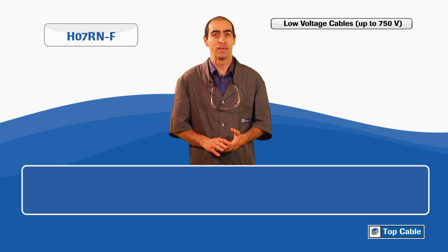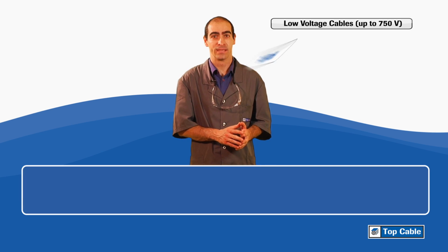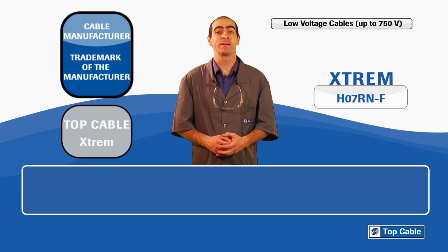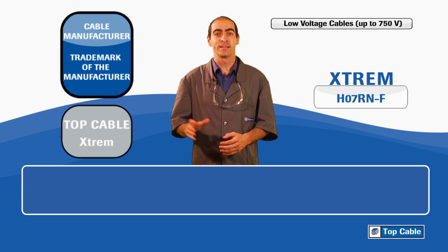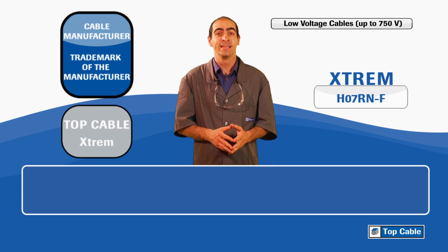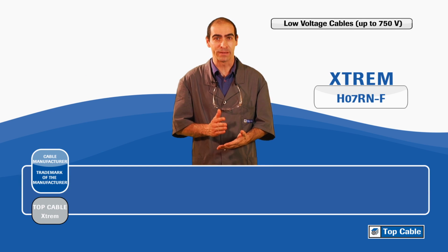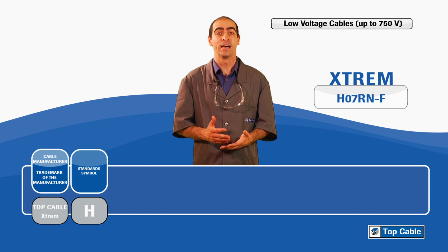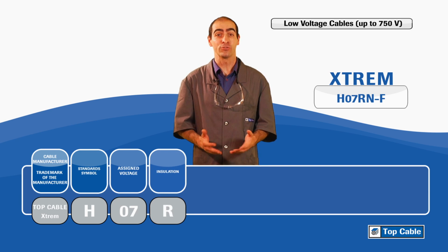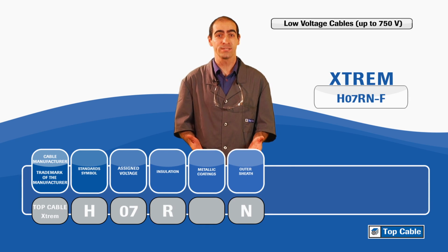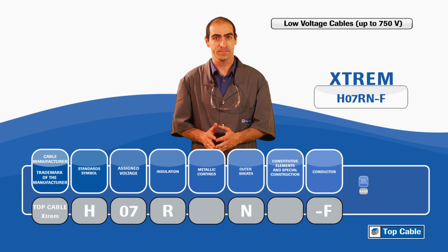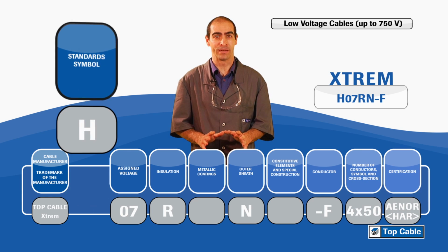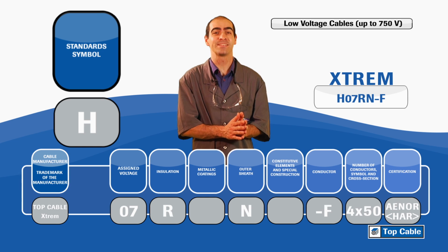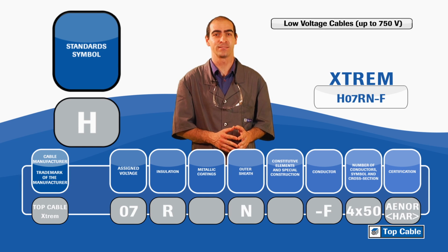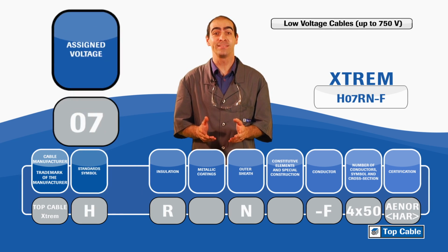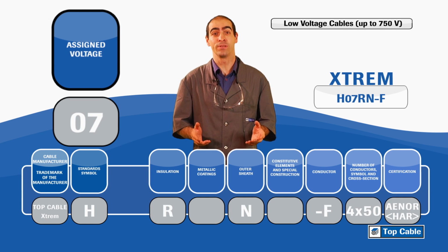Taking H07RN-F as an example, firstly comes the name of the manufacturer, in this case TopCable, and its trademark, Xtrem. After the name of the manufacturer and its trademark, the letters and numbers refer to its standardization, to the nominal voltage, to the cable insulations, to metallic coverings, to the type of conductors, and to the final composition of the cable. The meaning of each letter within each section is as follows. H means that the cable is designed and made according to harmonized standards. H, harmonized standards. 07 means its assigned voltage.